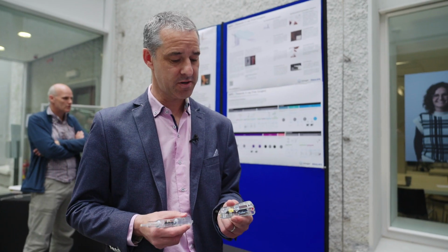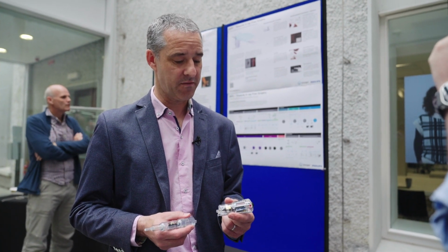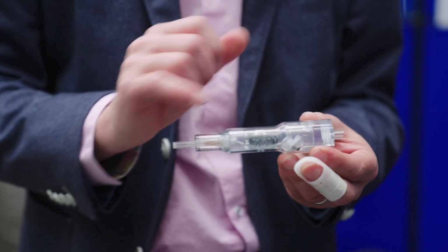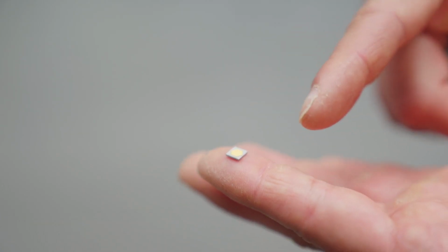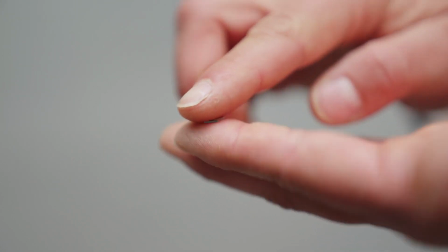This entire component, which comprises most of the valuable elements of the device, is entirely reusable, and this component, which is disposable, will be provided to the patient as required. There are many studies out there that show that there's a significant uptake in patient adherence levels once you engage with the patient. We work on the piezoelectric micropump in that device, so I actually brought one. That is our pump. It's only 5 × 5 millimeters large. It's actuated with a piezoelectric element.